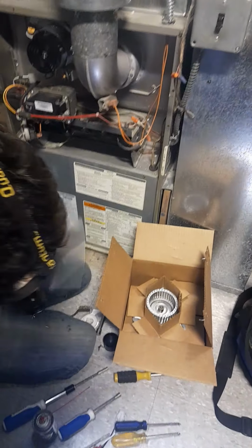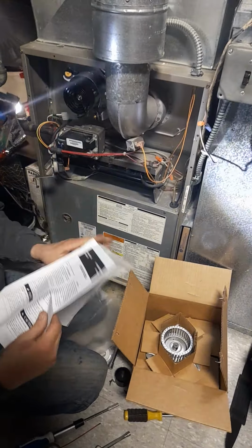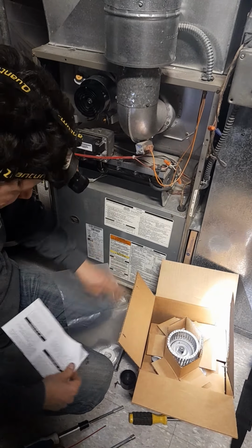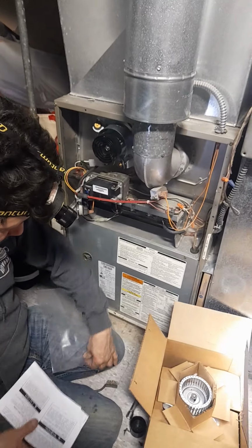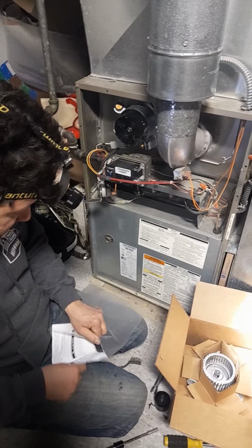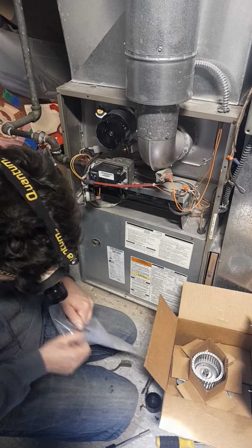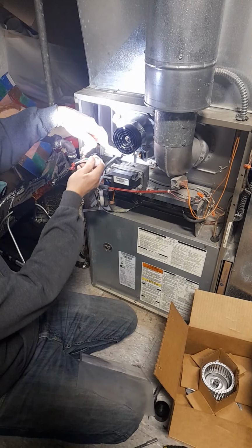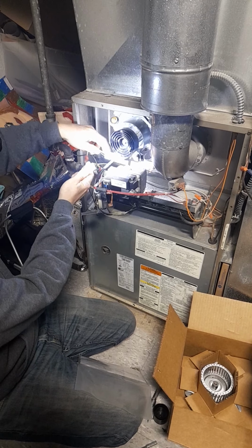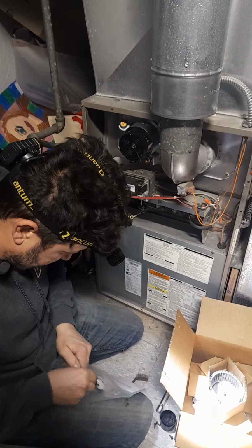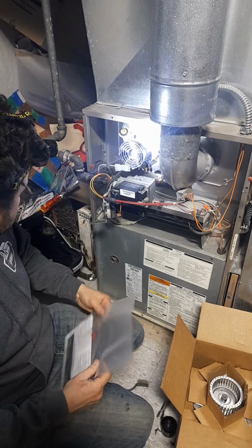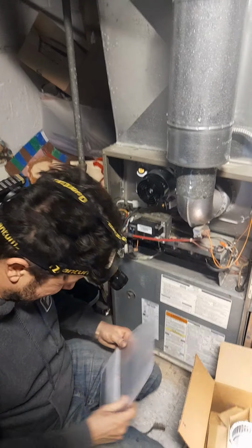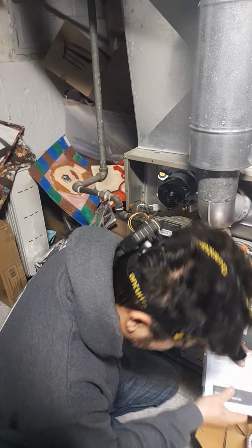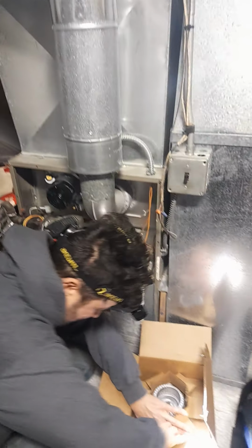That's that. This. And we needed the instruction manuals to see that we were supposed to tape that gasket in place, but there was a lip, so we just used that without the tape, because I don't think the tape and the heat from the collector box would probably goo up on us for next time. And there was no difference between the pigtail. It's the same one, same orientation, so I'm not even going to bother changing that. Okay. Here. 2 extra screws, I don't know what they're for. It's like Homer Simpson. Yeah, we'll find out. We'll find out when it flies apart. No, I'm just kidding. It's probably for when you drop it. Yeah. It's for the extra ground screw problems that you run into.